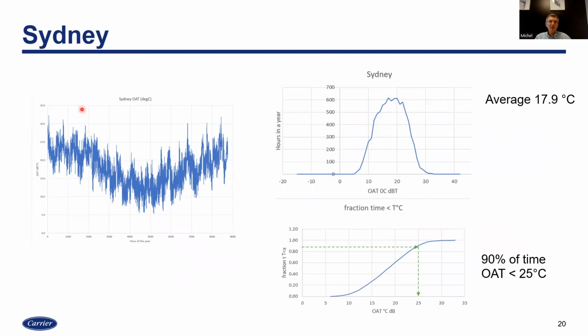So I took, for instance, Sydney. If you look at those data, it's a little bit hectic. But if you sort them, you will see that there is a distribution of temperature. We call these bins, and you will see that in Sydney there are very few temperatures above 35. There is almost none below 5, and the average is somewhere here. This is the number of hours. You will see that there are exactly 600 hours in Sydney when temperature is 20 degrees C, and probably 300 hours when temperature is 10 degrees. But if you take the average, 17.9.